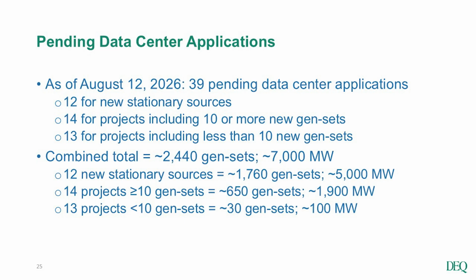14 for projects at an existing data center that includes the addition of 10 or more new gensets at that data center, and then 13 are projects where the data center is planning to add less than 10 new gensets at that particular facility. And for this collection of applications, this represents approximately 2,440 new gensets, with around 7,000 megawatts of new capacity. And the majority of that is occurring at the new stationary sources.